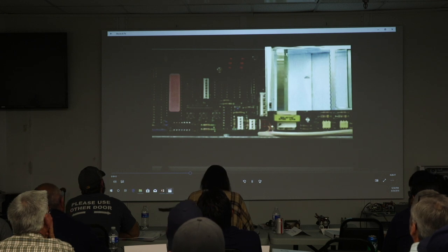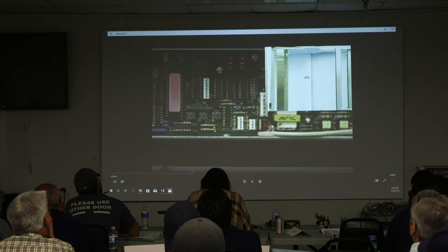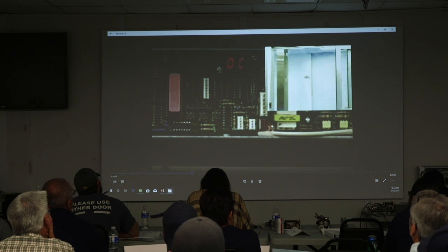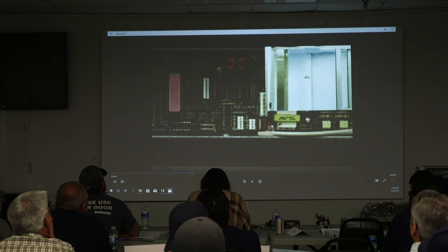control. Braking is necessary to slow the door prior to full open because it is desirable to clear the door from the opening as quickly as possible to facilitate traffic. When the control determines the deceleration is complete, the braking signal is removed and the control goes to open check speed until open cushion is reached.